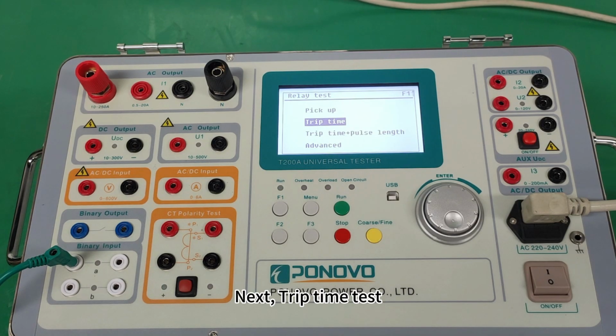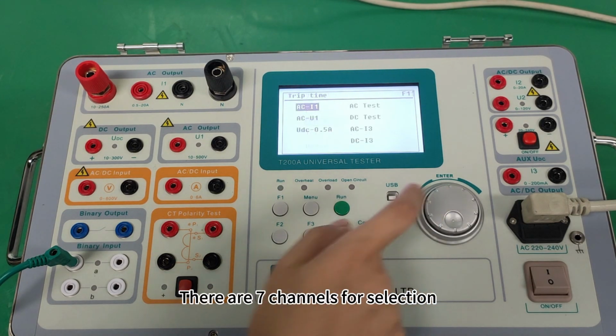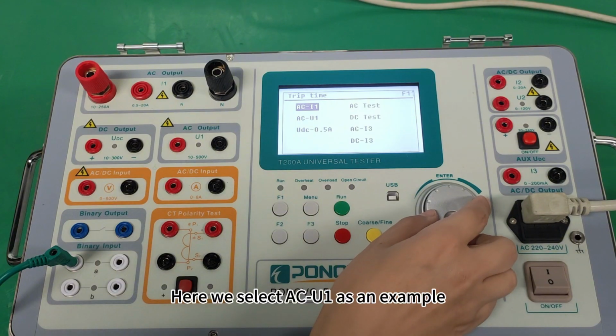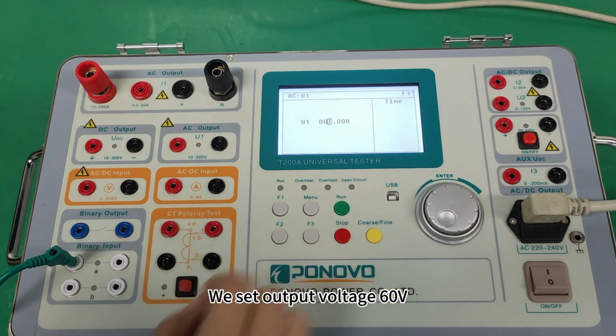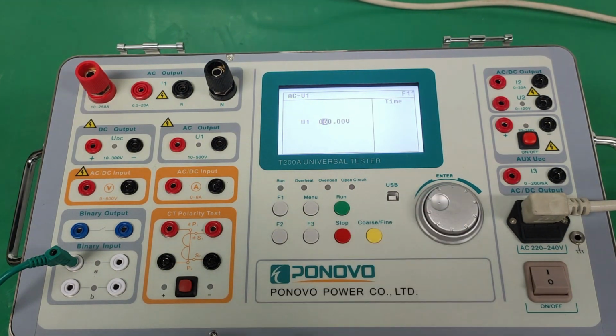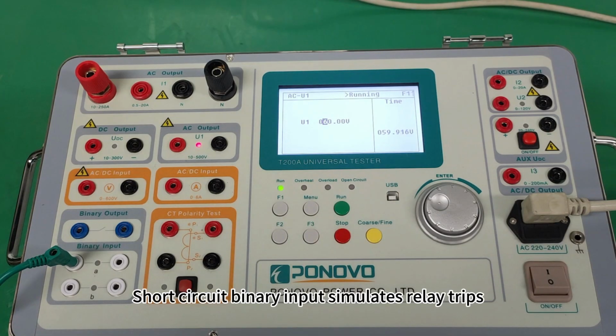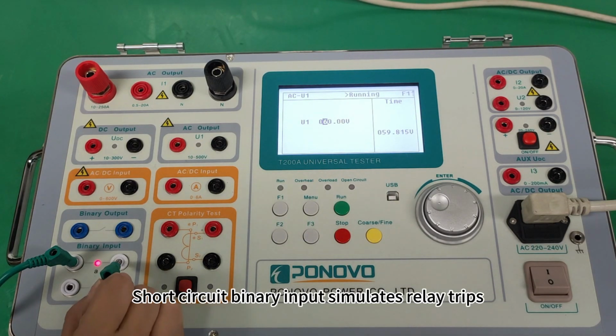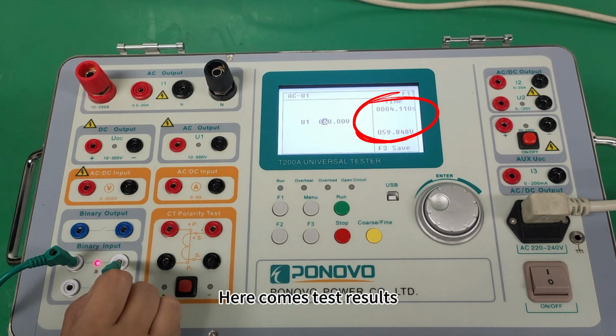Next, trip time test. There are 7 channels for selection. Here we select ACU1 as an example. We set output voltage 60 volts. Press Run button. Short circuit binary input simulates relay trips. Here come test results.